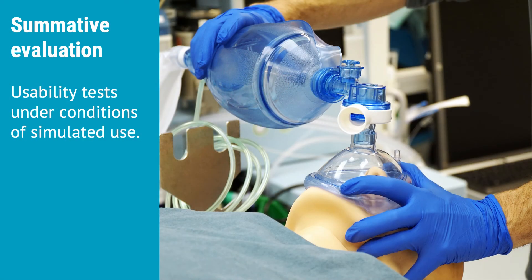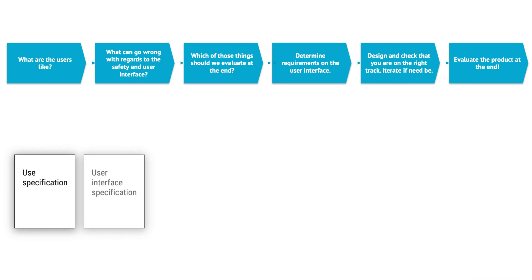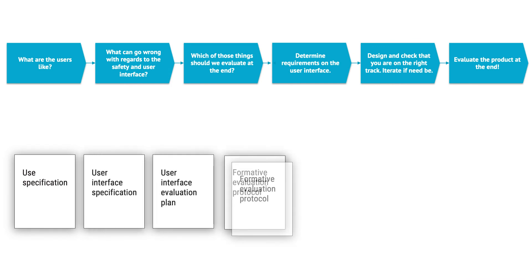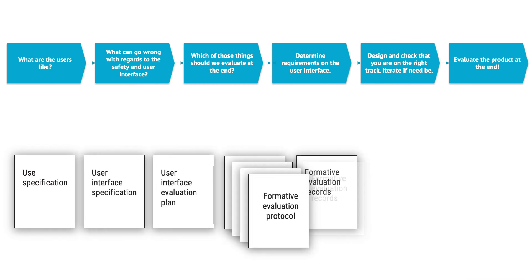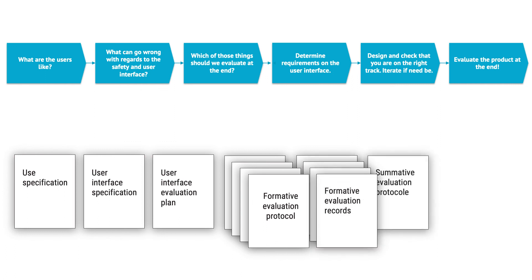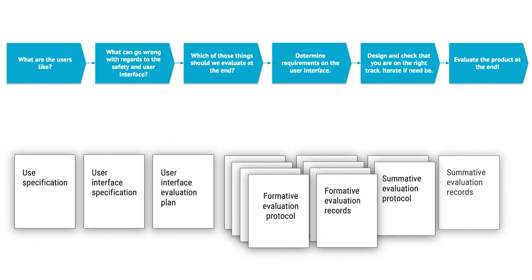Summative evaluation is testing usability under conditions of simulated use, using production units or equivalent devices. It's similar to design validation in method, but the purpose is different. Finally, all the documentation and records created throughout the usability engineering process are referred to as the usability engineering file.